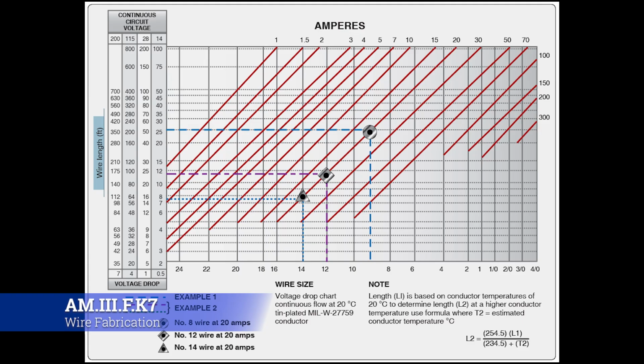Okay, so now we have that out of the way. Let's talk about how we go about actually selecting the wire. We know all the engineering specs of the types of wire we could use, so which one are we going to decide? First, we want to prevent excessive voltage drop for a required current over distance, meaning we need to select the right wire for the right job so we don't drop the voltage, even though it's connected, and all of a sudden the lamp doesn't come on. It's because we chose a wire that's going to shed tons of voltage, and it's become a big resistor rather than the appropriate wire for what we're using.